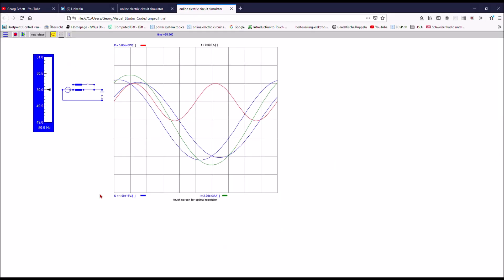This is now an example on the simulator. You see a generator that is our model we used before. Now I have two lines in parallel and I'm relatively close to the tipping point with the power. And if I lose now one of the parallel lines, you see how the generator gets accelerated more and more uncontrolled.